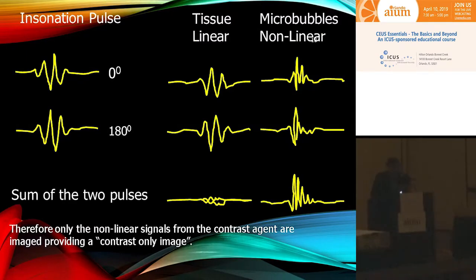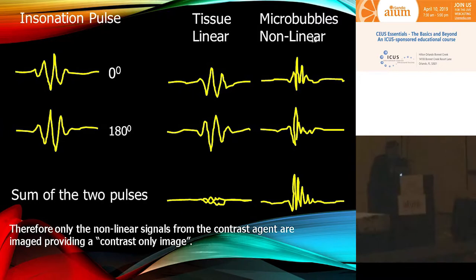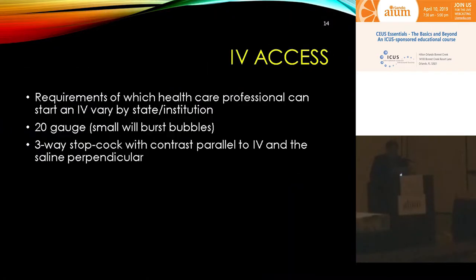With pulse inversion — the simplest technique — we send in two pulses out of phase from each other. The linear signals subtract and have no signal, but the non-linear response gives us signal. If we subtract the out-of-phase images instead of adding them, we get a B-mode image, which some vendors use as their real-time B-mode. That B-mode image may not be as beautiful as non-contrast B-mode because SonoCT, harmonics, and other features are shut off, but it is truly a real-time image from the same information used for the contrast image, so you can be confident you're looking at the same location.